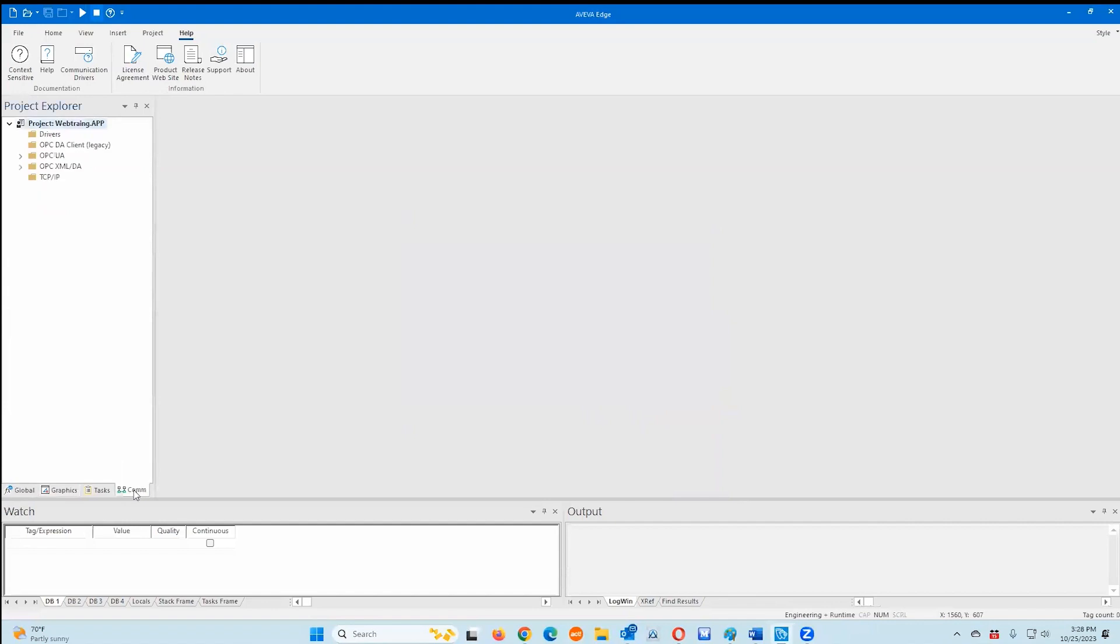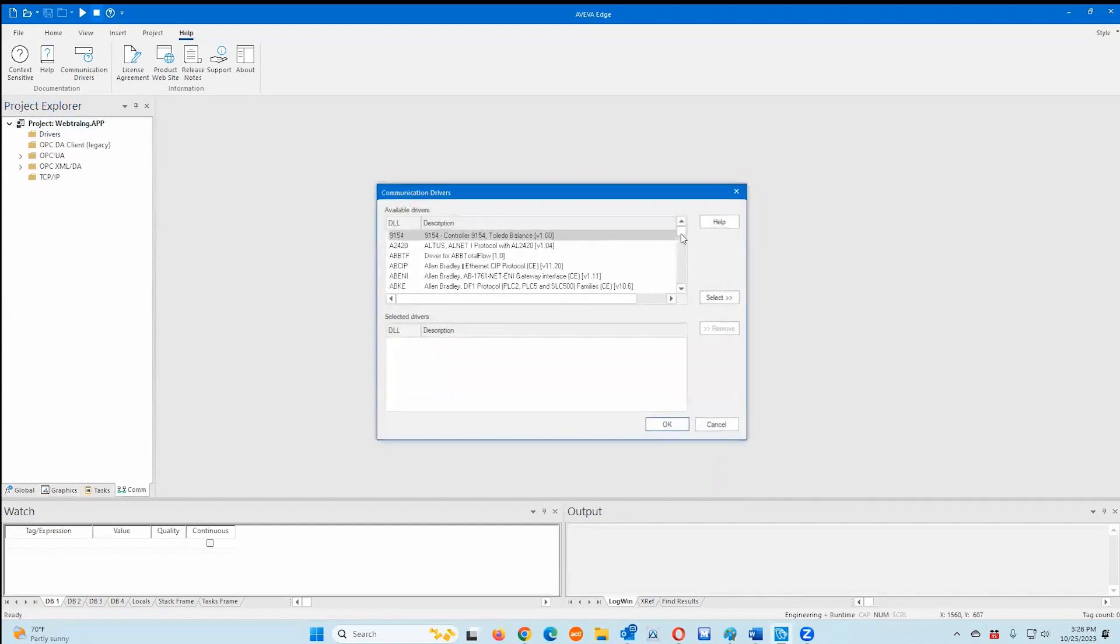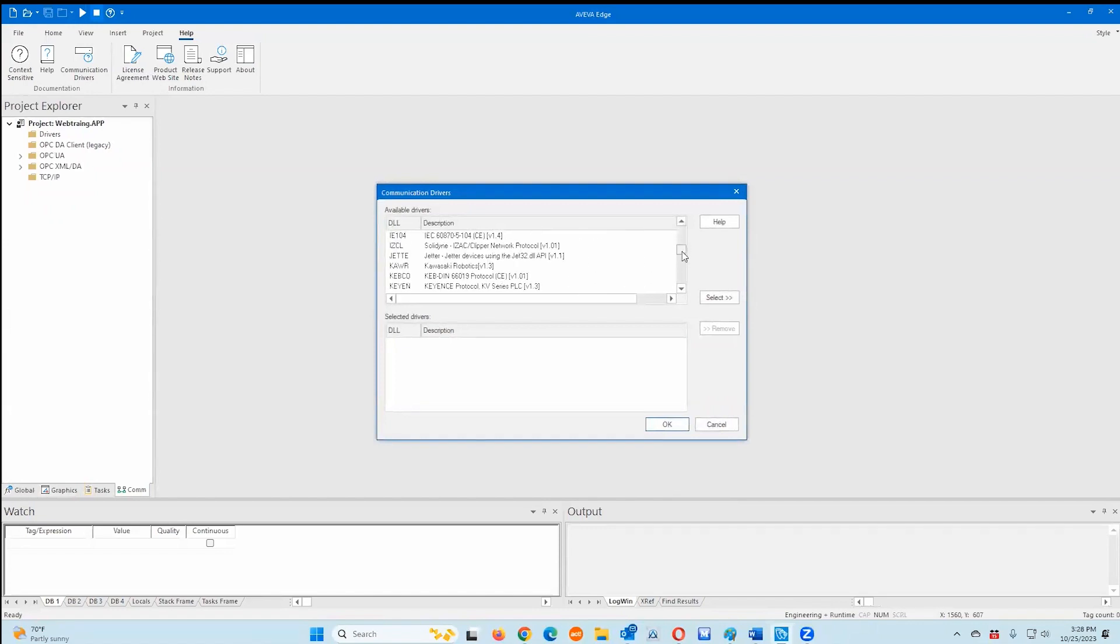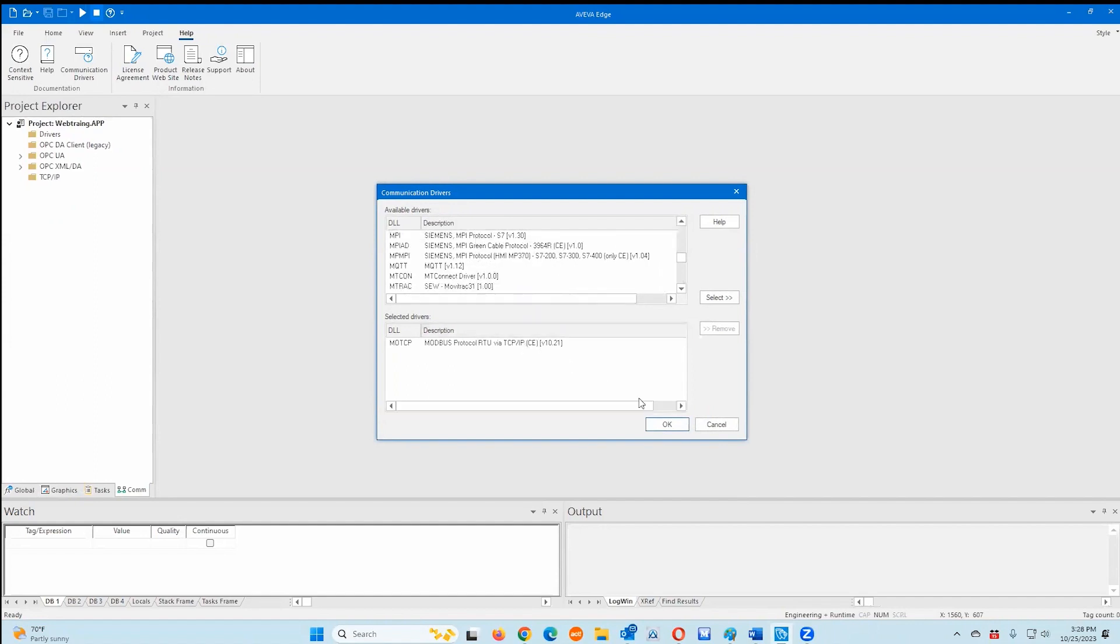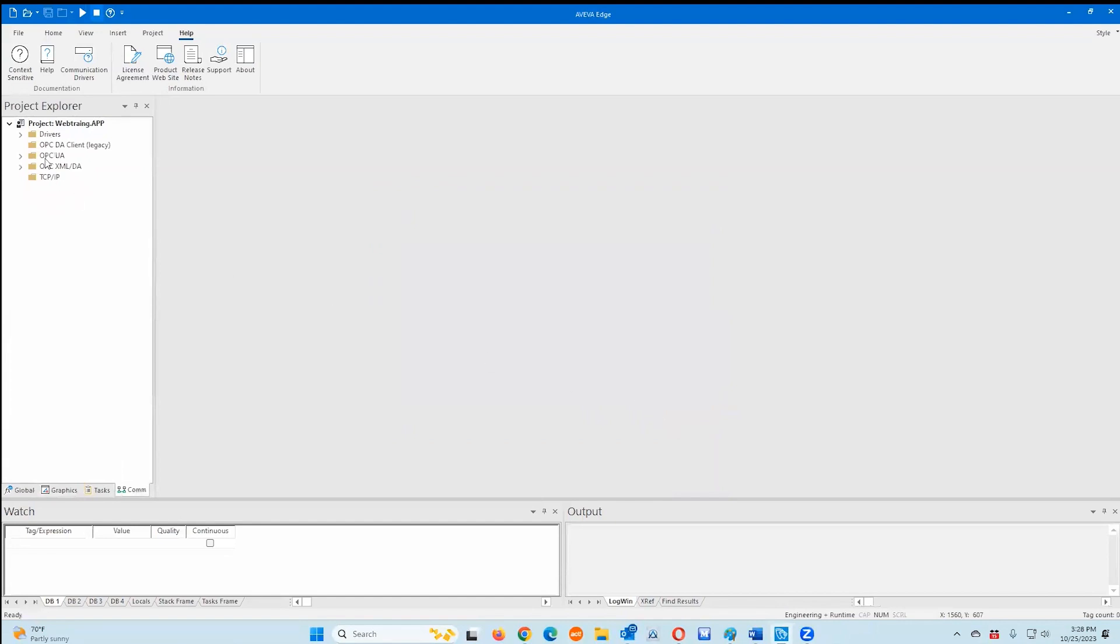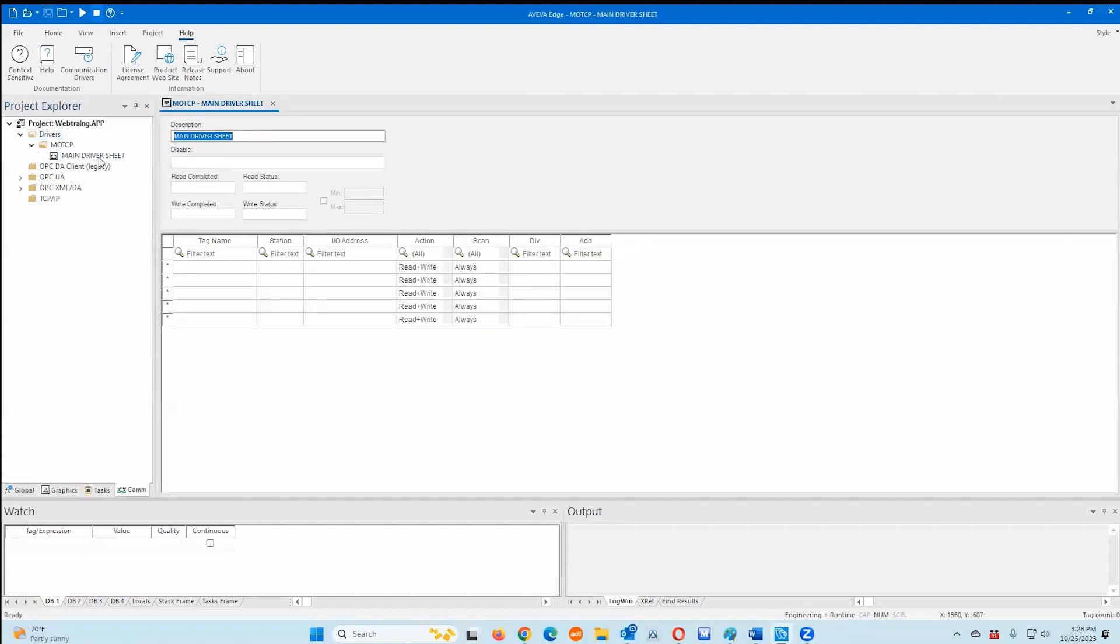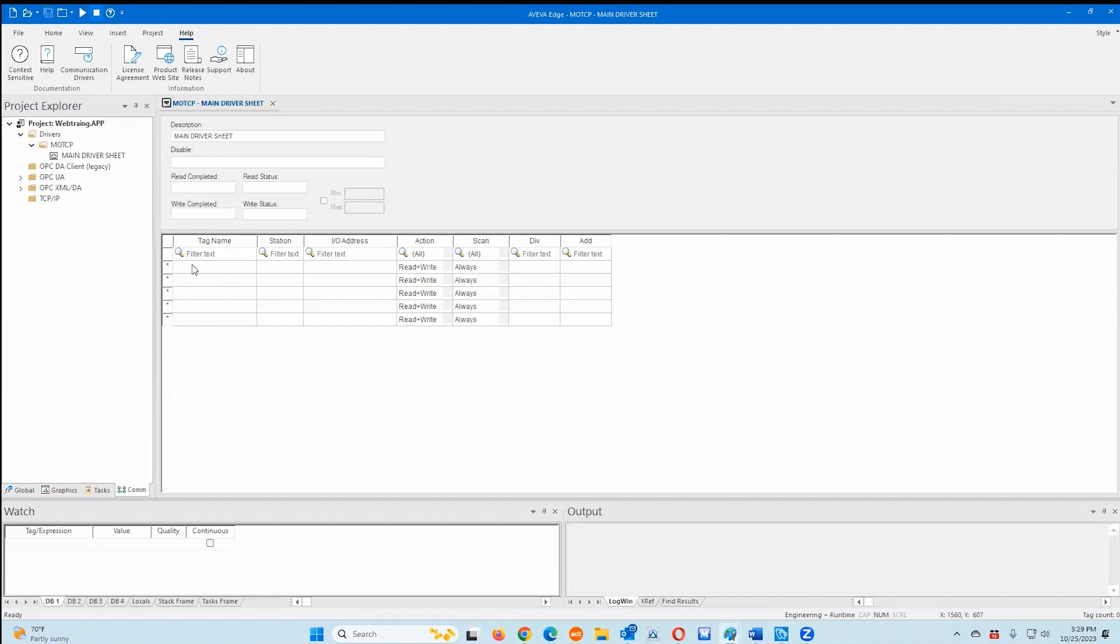Okay, so the first thing I want to do is create our connection to the Modbus TCP data acquisition module. So first thing I want to do is add a driver. I want to go here and select my communication driver. For this one I'm going to use Modbus TCP. We want MOTCP here. It's added down here. I click OK. Then we need to open up the main driver sheet, which is created because I added that driver. My main driver sheet will look like this. From here I need to add and create my tags. And I need to create the connection, which shows the station number, the IP address, and the port 502, along with the address, which is achievable or findable in the Modbus register table manual.